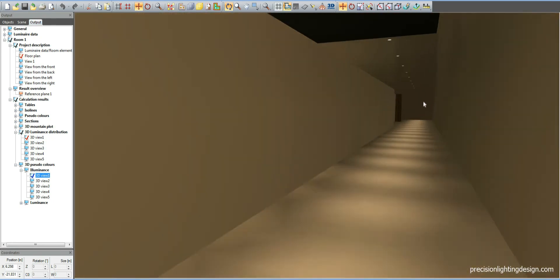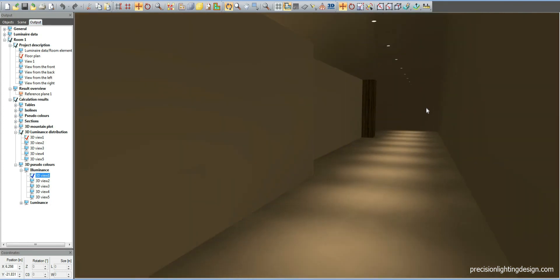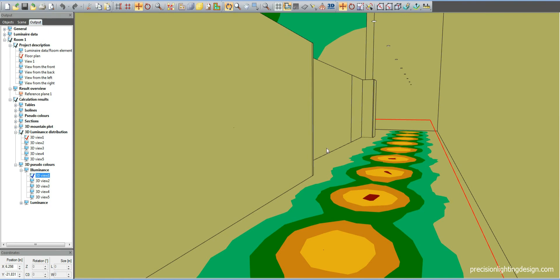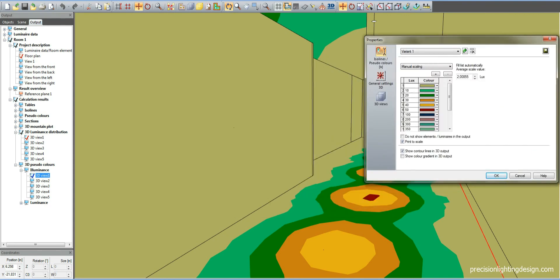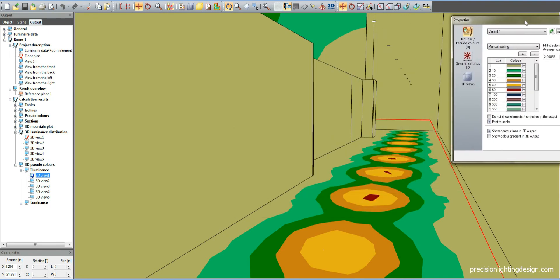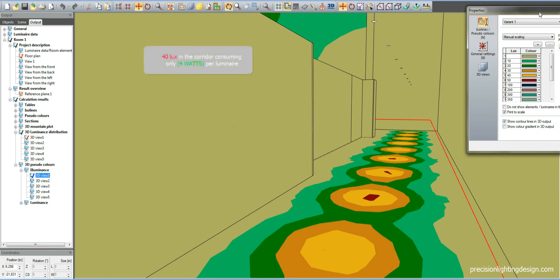As we move along the corridor, you can see that the lighting is designed to lead the way. There is 40 lux of light on the corridor, while consuming only 4 watts of energy per luminaire. That is huge amounts of energy savings.